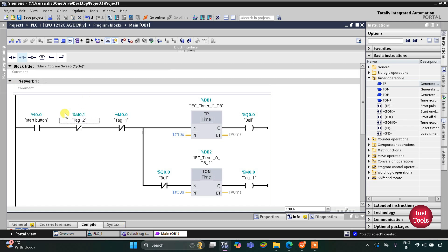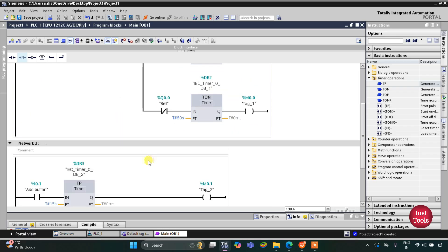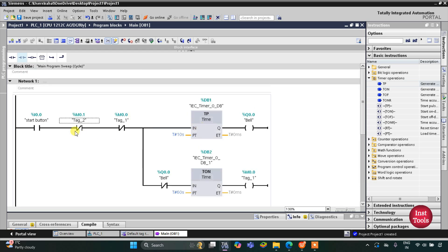So what happens: when the start button is turned on, the bell gets on for 10 seconds. After 10 seconds, the bell gets off and M0.0 gets on after 60 seconds. When M0.0 gets on, current stops flowing through the normally closed contact, causing the TON to reset, and then the bell turns on again. If the add button is pressed, M0.1 gets on for 15 seconds, and during those 15 seconds the bell will not turn on.